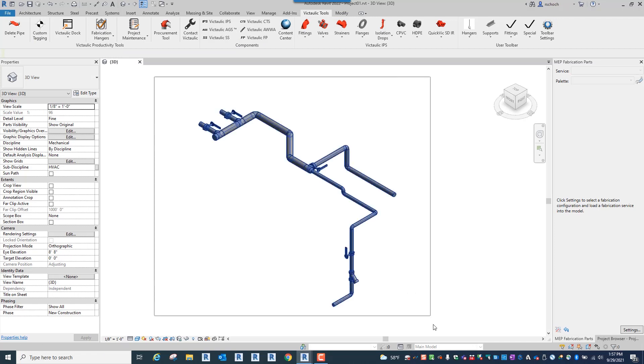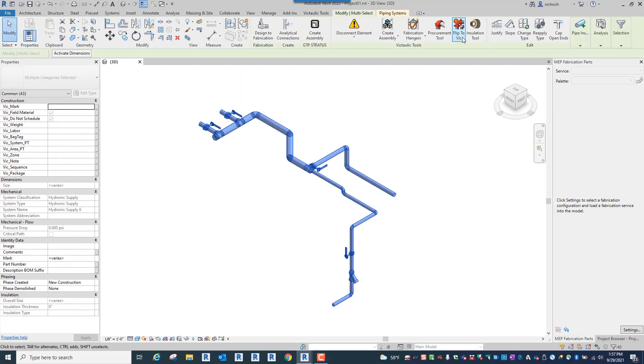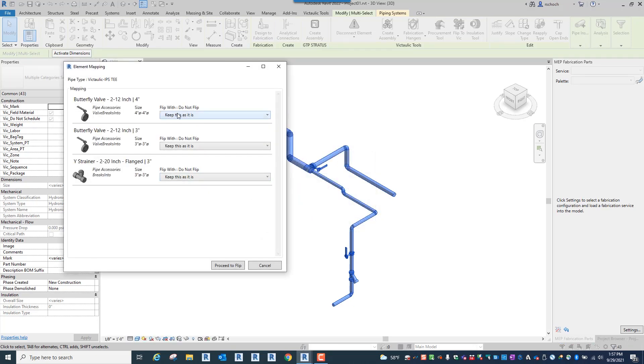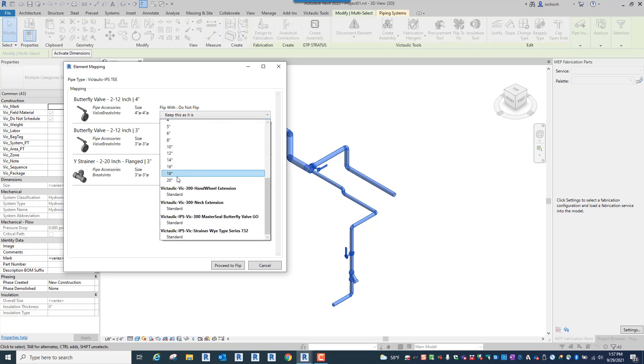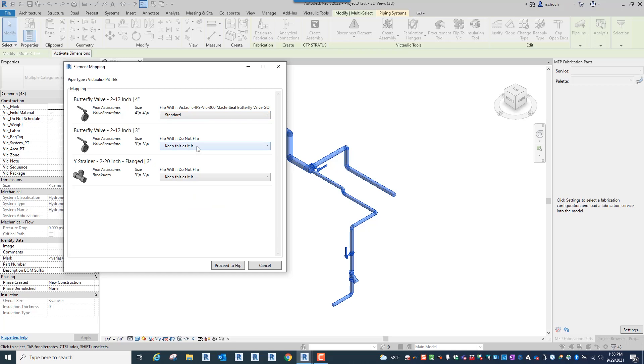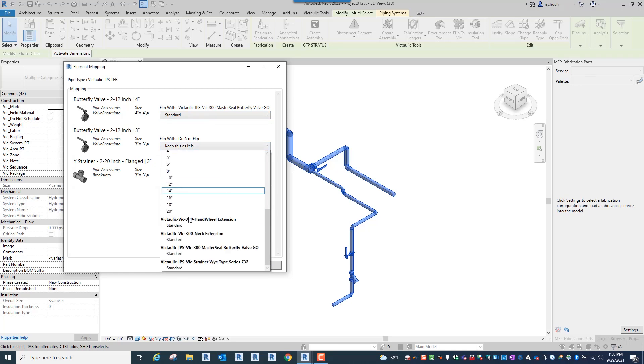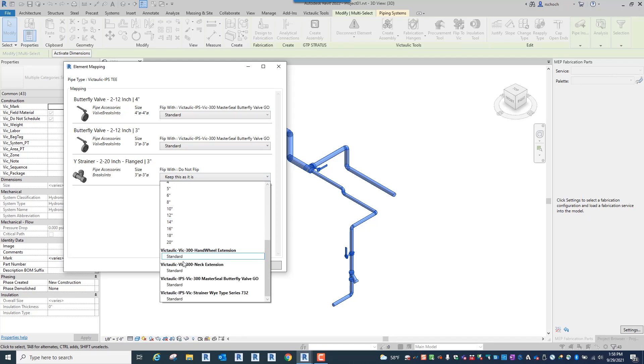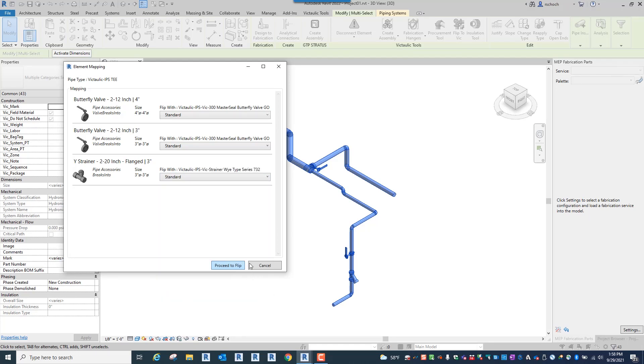Now watch this. When I select the model and I go to Flip to Vic, you'll see here I can just leave it on IPST. I can click OK and now I have the option to come down here at the bottom and set a Vic 300 gear operator butterfly valve for that. I can set another gear operated butterfly valve for that. And then for the strainer I can come down here and set the Y strainer or 732 Y strainer. So what's nice with Flip to Vic is it's going to remember these selections that you have here. So the next time I come into Victaulic IPST and I want to do a flip it's going to remember hey last time when you saw a pipe accessory of four inch you selected a gear operated valve.